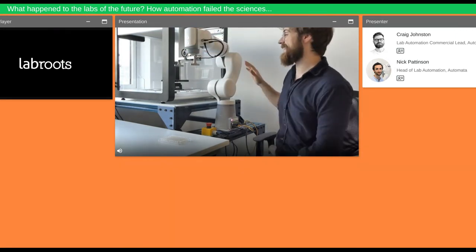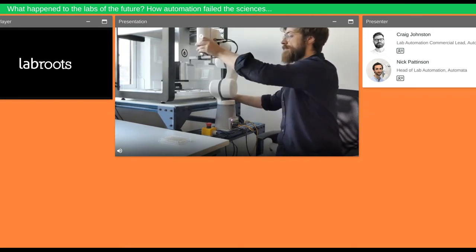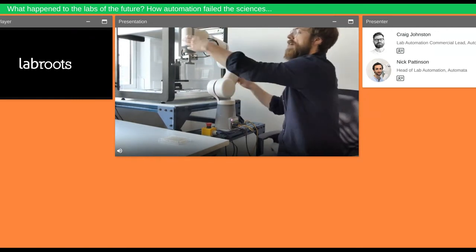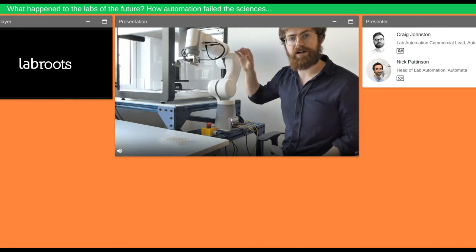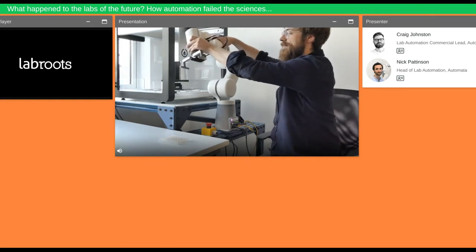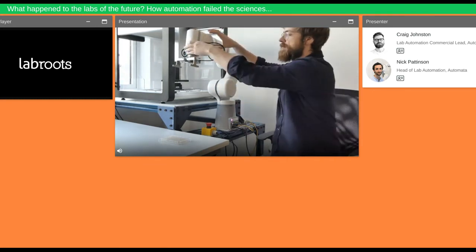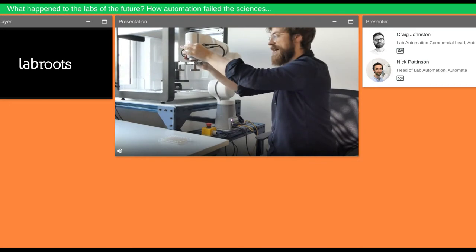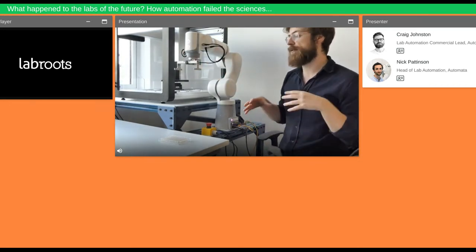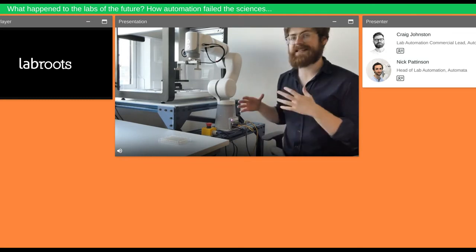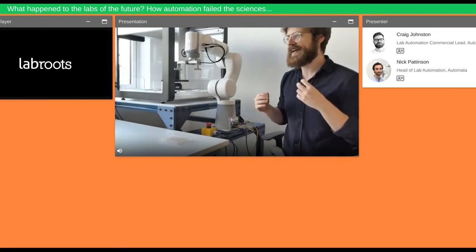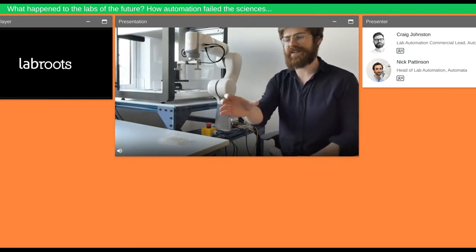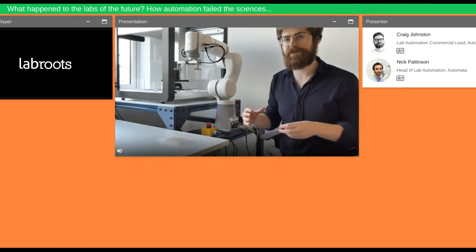So EVA is a six axis industrial robot. So it has six joints. We have joint one down here, which is a big rotational joint. We have two and three here, which is your lean forwards and back joints. We have joint four here, which is just like your forearm, it's a rotational joint. So it can go in and around like that. We have axis five here, which is very much the wrist of the robot. So it's an up and down movement just there. And then we have axis six, which is your final rotational axis here. And those six axes give you six degrees of freedom, which gives you ultimate flexibility in automating your assays. So that makes it easy to move things from different levels, say from a lower lab bench up to the bed of the Opentrons here. It helps you manipulate in and around microplate readers if they have cartridges coming out. It just gives you that ease of movement to get in and around everything you want to automate around.